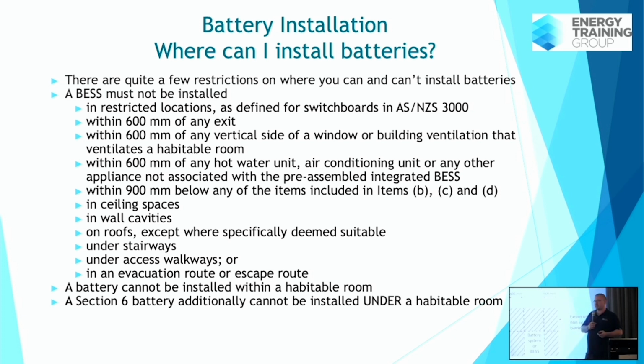Another very important thing to consider is fireproofing. If a battery is installed on a combustible wall, it must be fireproofed: 600 mil either side and 900 mil above. Ideally, you just don't want to install on a combustible wall.